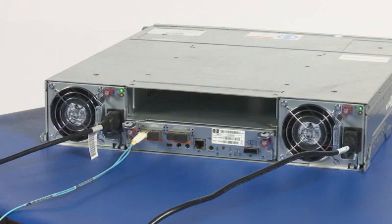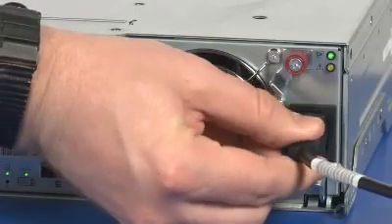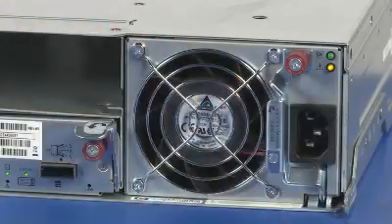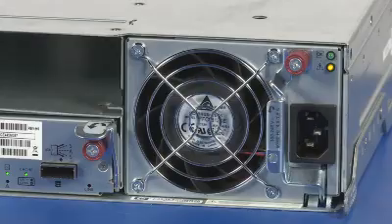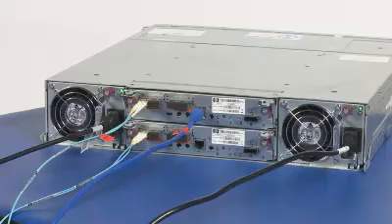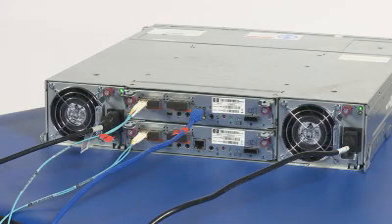Removal. If you are replacing a controller in a single controller environment, stop all I/O and remove power from the enclosure. Go to Step 3. In a dual controller configuration, to shut down the failed controller, access the SMU.